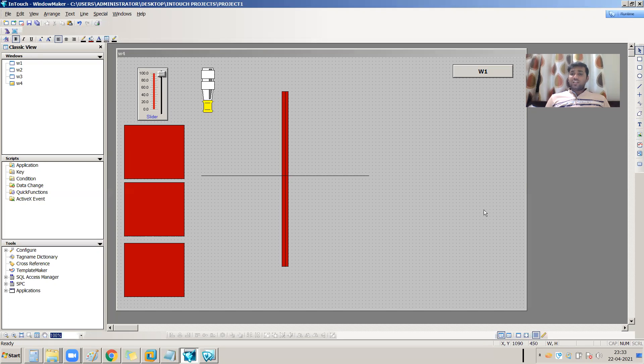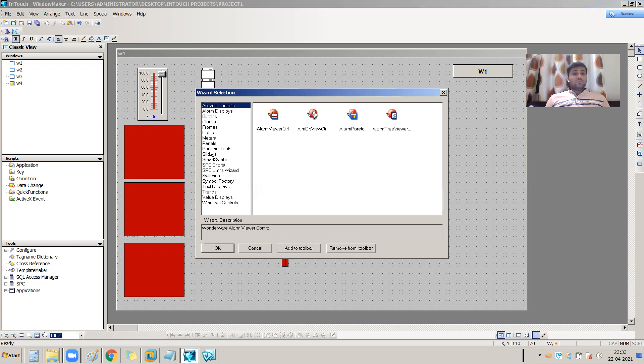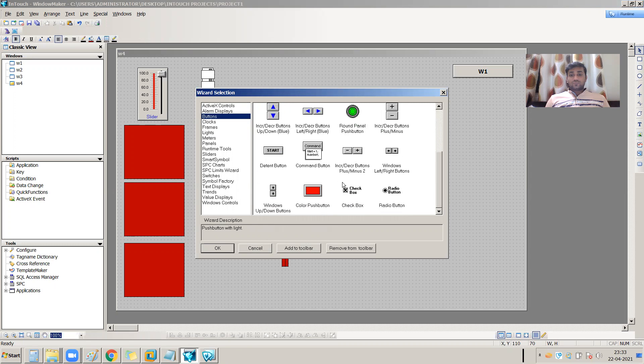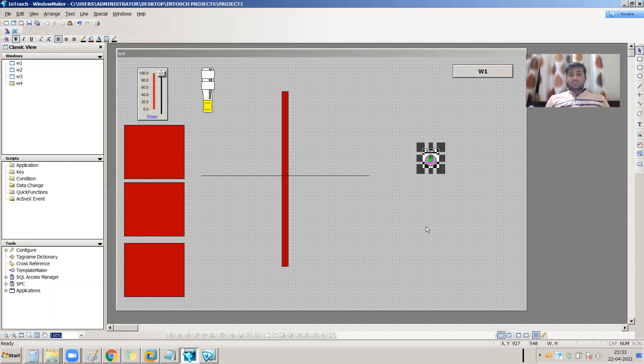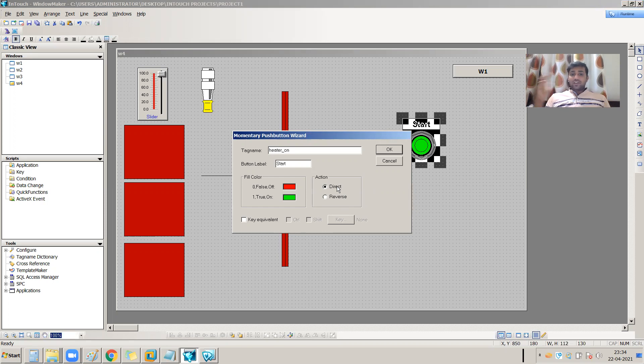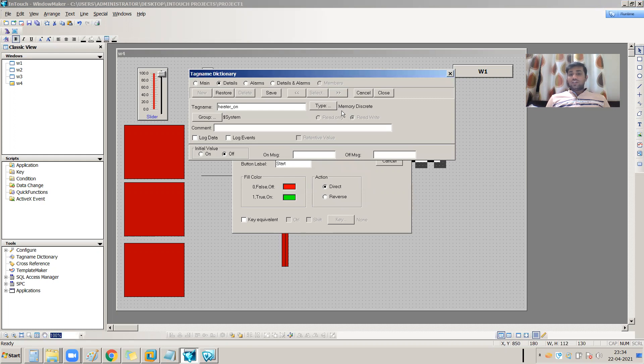For example, let's make one object in an operation. I am going to take one button - this is my start button. I am going to attach a tag called Heater On. Whenever I press the button my heater will turn on, and whenever I release the button my heater will turn off. I'll define the Heater On tag as a memory discrete, because it's a digital tag, and save it.